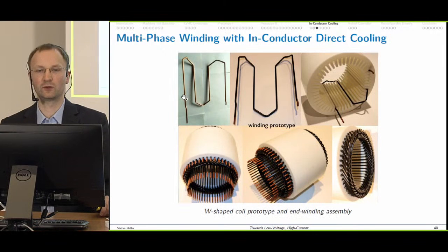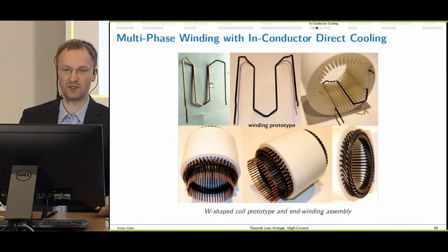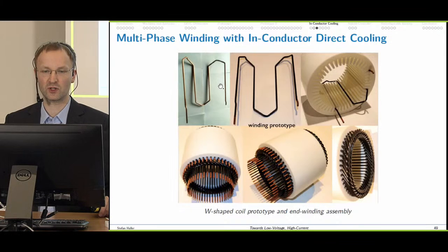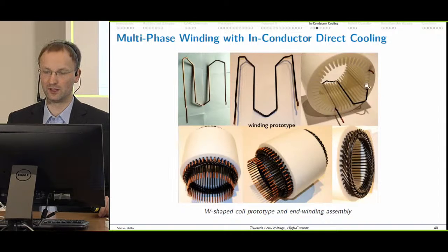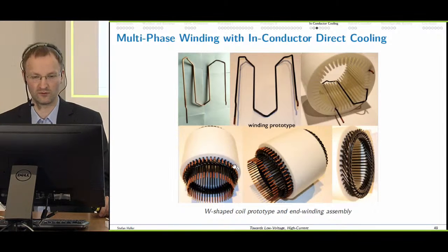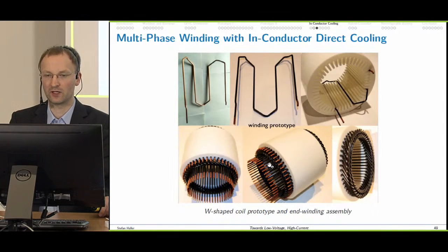This is the conductor during the production and assembly process. Here we see it out of the bending machine. This is with ceramic insulation coating, and here is one of the coils inside the plastic mold. Here we see the assembled machine's winding in the plastic mold. All 48 are in place. Power electronics will be hooked up here, and this is the machine's end winding here at the back.